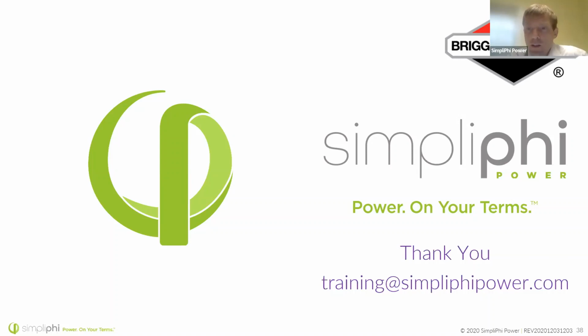Ross says, thank you. I learned a great deal from practical sizing and safe usage. Is it safe to assume all batteries are sized similarly so that 24-volt batteries have a similar power curve that drops off from 28 to 30 volts down to 25? Yes. So Ross, if you just divide the 48-volt characteristics by 2, you'll get the 24-volt characteristics.